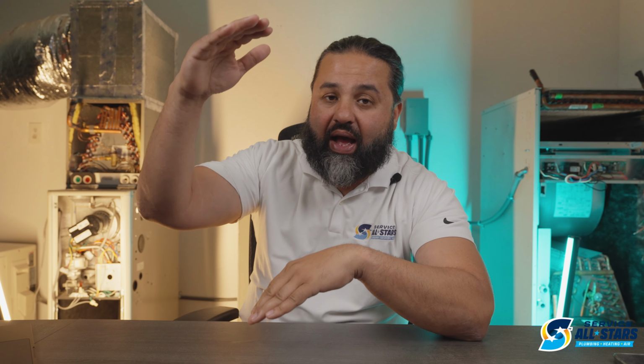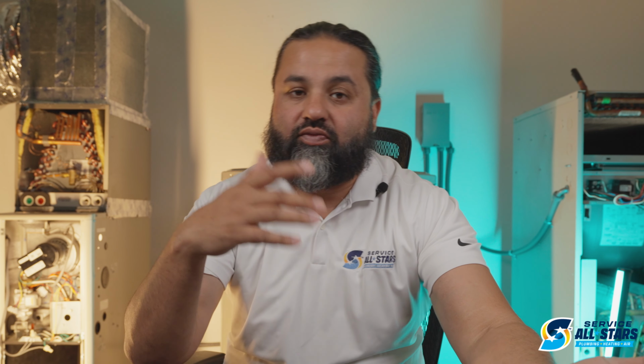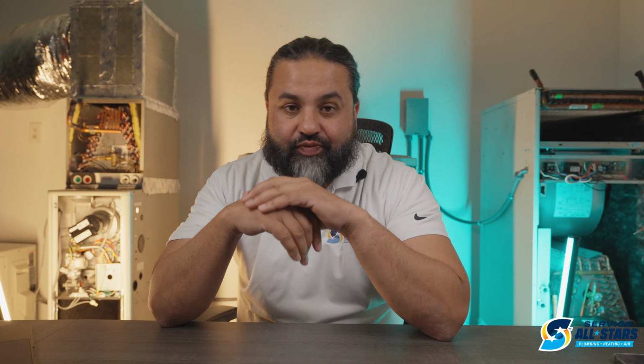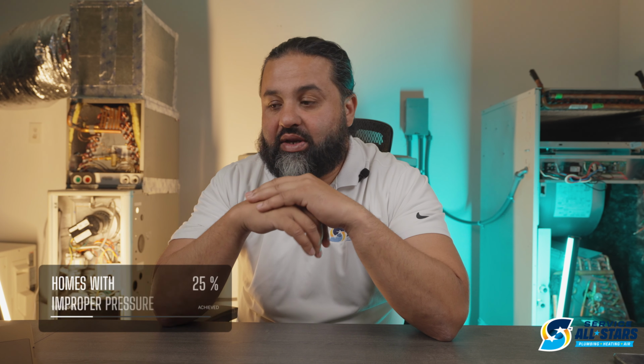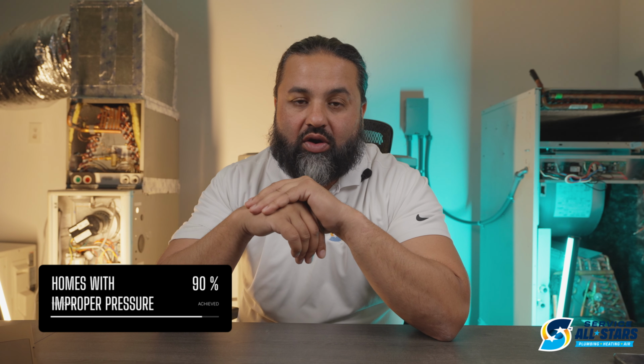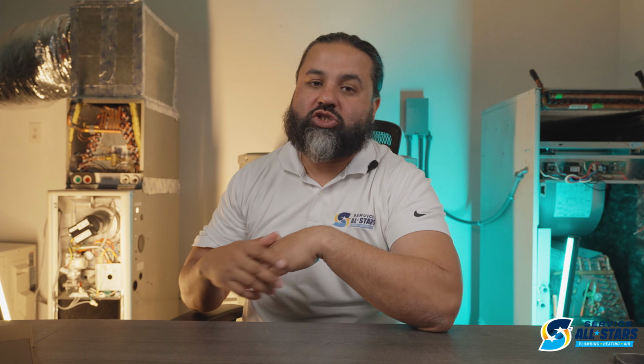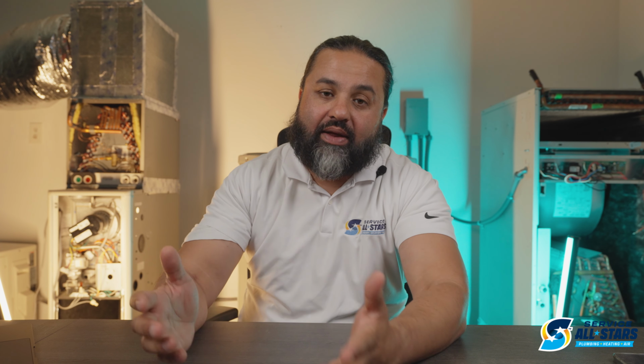It varies between systems. But what happens with static pressure is that if the static pressure is too high, your system is not going to operate at optimal levels. And what you're going to have is a system that works but really doesn't perform. And so improper static pressure is in 90% of all homes out there, wherever HVAC is installed, really is lacking from high static pressure. And what we like to say is that static pressure is like the blood pressure of a human body. So static pressure and blood pressure can be related very easily.